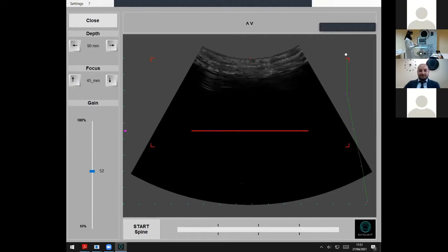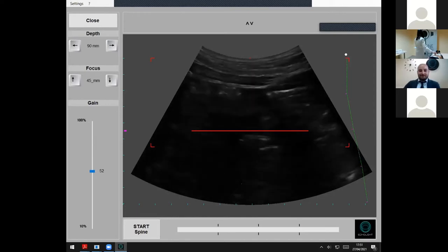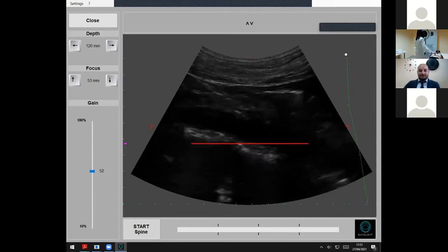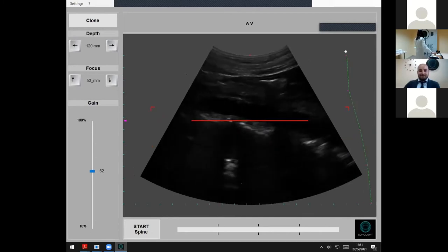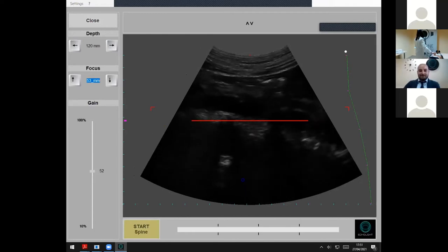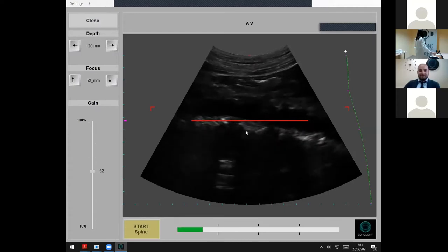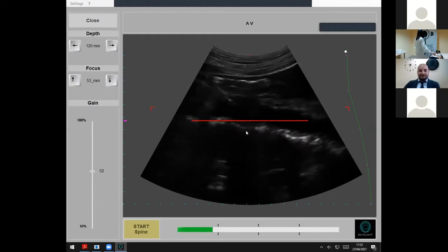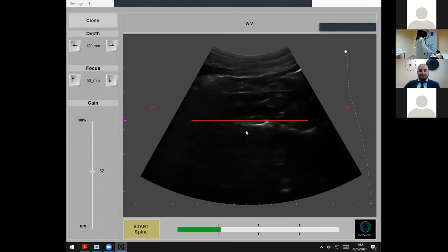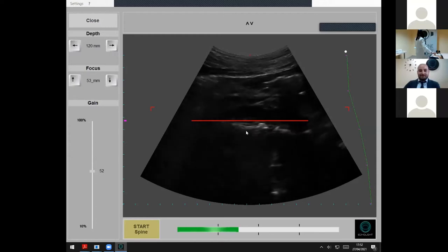As you see from the echographic cone, what the operator needs to check in order to perform the acquisition are just two parameters, the depth and focus, that will allow the operator to put the bone interface that you can see here in the center of the echographic cone and as much as possible attached to the focal line, that is the red horizontal line, in the center of the echographic cone. So the beam of image must be in the center of the cone and within the focal area that is delimited by the four angles that you see on the side of the screen.